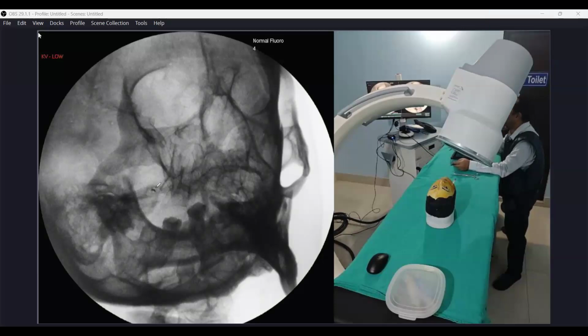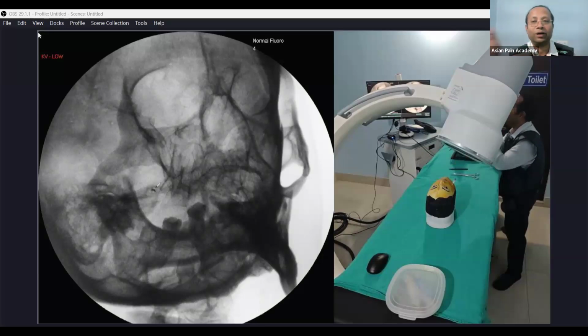With the spinal needle, we can't do it, right? No, then electricity will go everywhere, because it is conducting everywhere. In an RF needle, what happens? The active tip is open, and electricity comes out from there, in the active tip, not in the other part that is insulated.